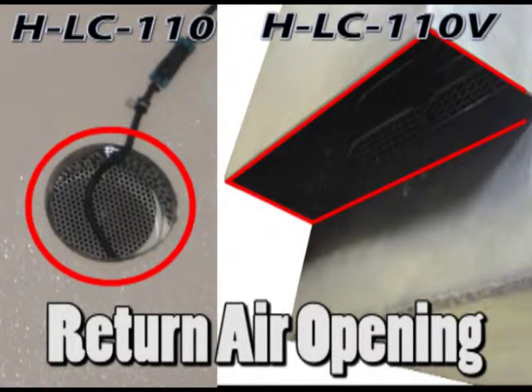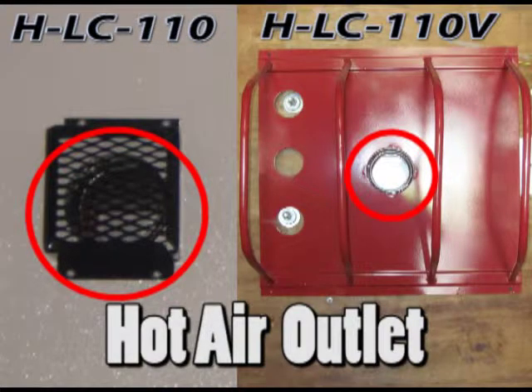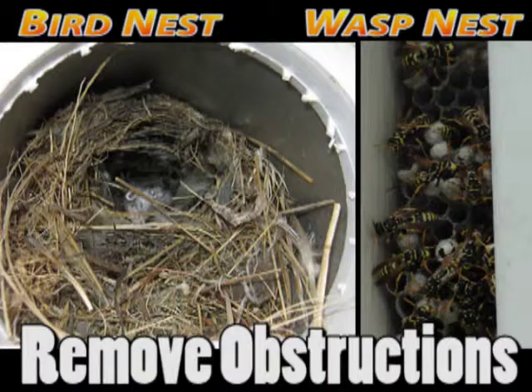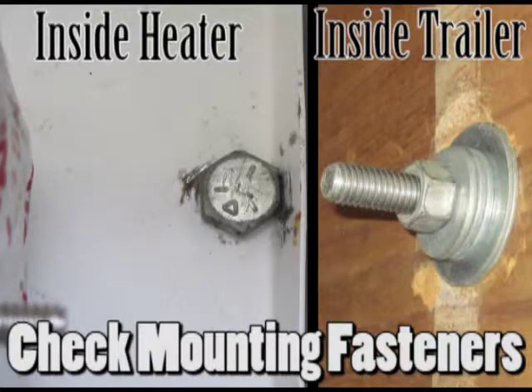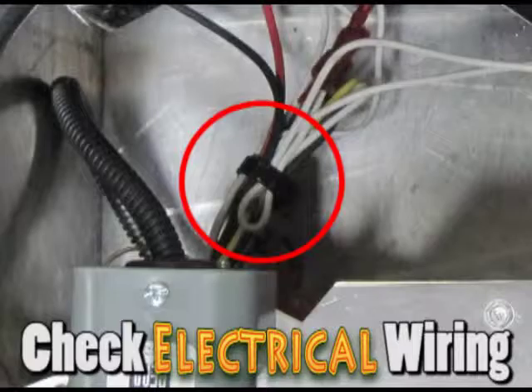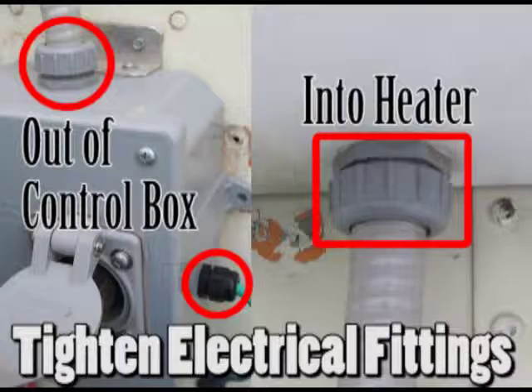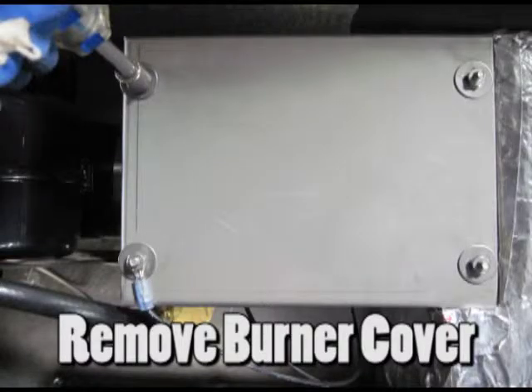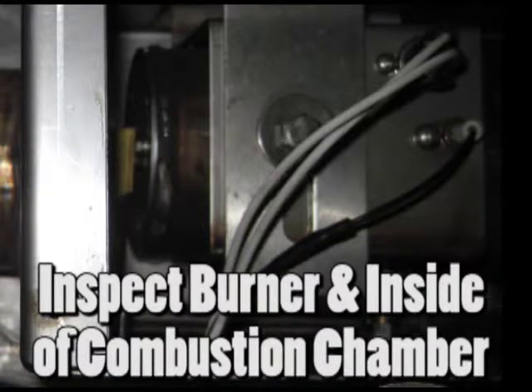Check the return air inlet and the heater outlet for damage and obstructions. Remove any obstructions and repair any damage. Check that all mounting bolts and screws are tight, and check that all electrical wiring is securely attached and undamaged. Also check that electrical fittings going into the heater and control box are tight. Remove the burner cover and inspect the burner and the inside of the combustion chamber.